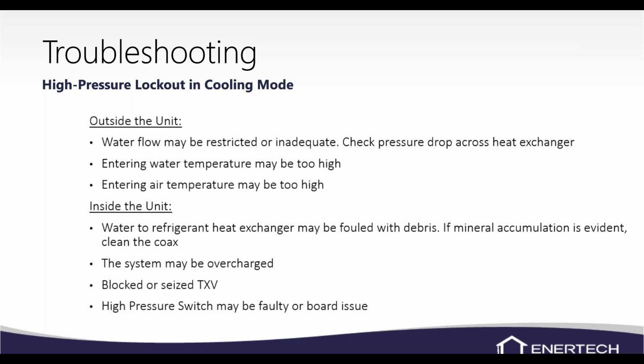One thing that is good: if the high pressure switch fails and it's not leaking refrigerant, we do have a high pressure switch kit. We have a low pressure switch kit as well, and it'll thread onto your access port, your service port, with a T, and then we can thread on a new high or low pressure switch and still be able to check refrigerant pressures. So the only time we really need to get into the refrigerant circuit to change a high or low pressure switch is if it's leaking refrigerant.